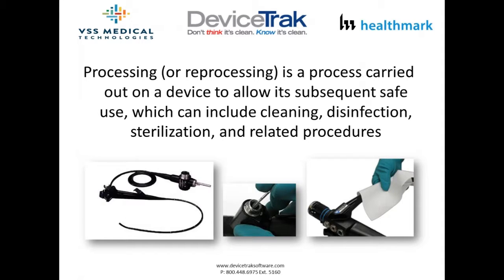Let's talk about what processing or reprocessing is. Currently those terms are used interchangeably. Within the current AAMI standard ST-91 for endoscope reprocessing, we did land on the word processing. What that means is the steps or the entire process carried out for an endoscope or any other type of device that allows it to be safe for the next patient use. Reprocessing encompasses everything from pre-cleaning after the procedure through proper drying, storage, and labeling.